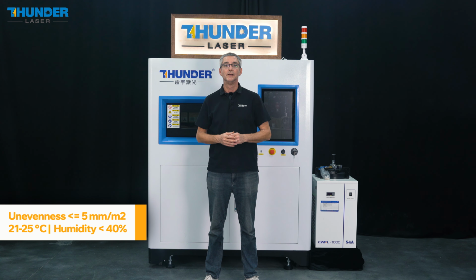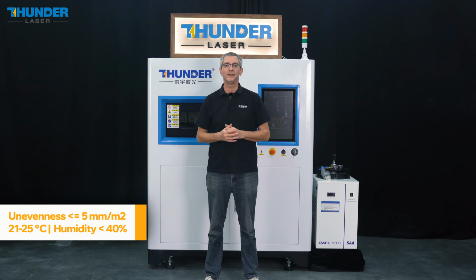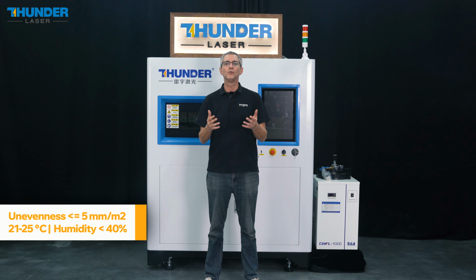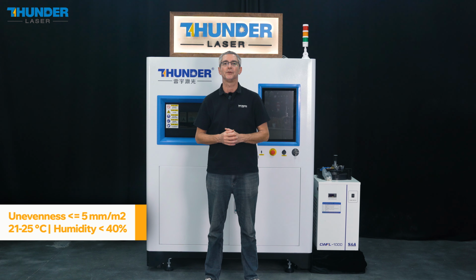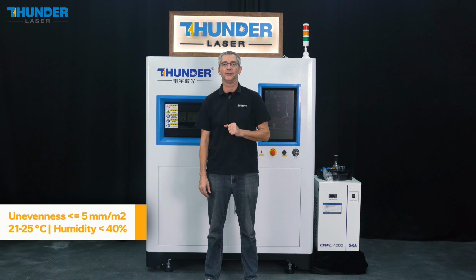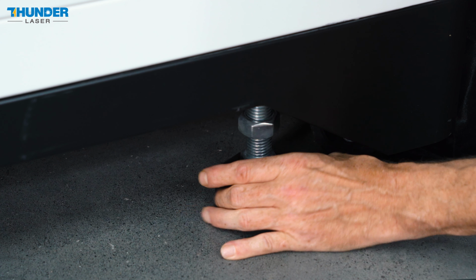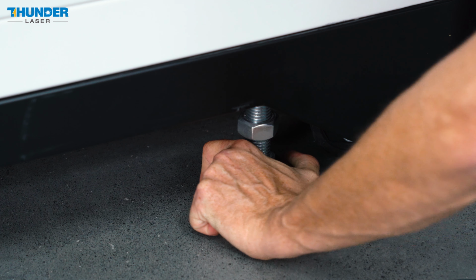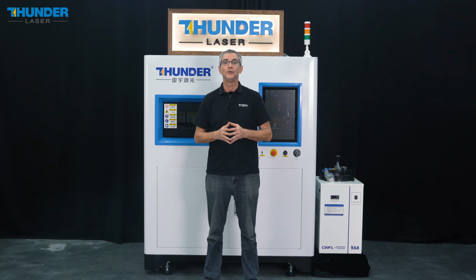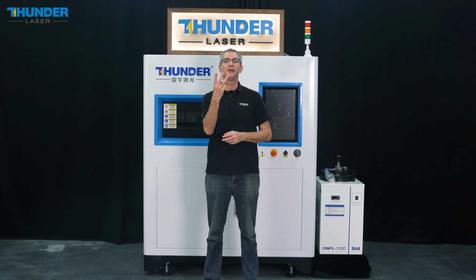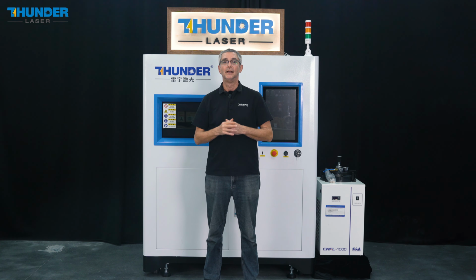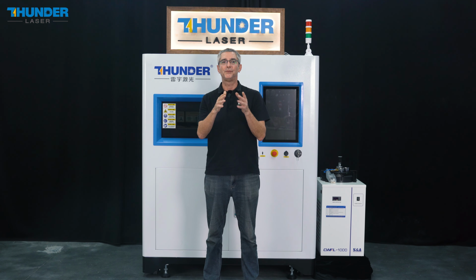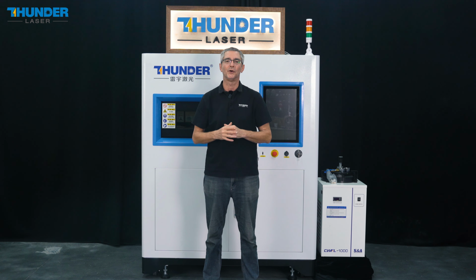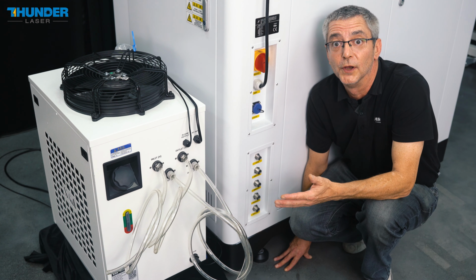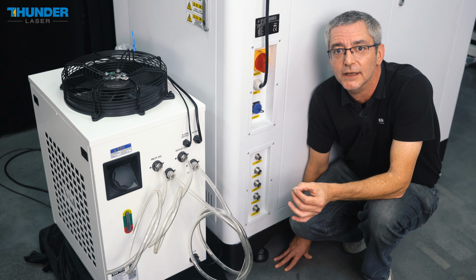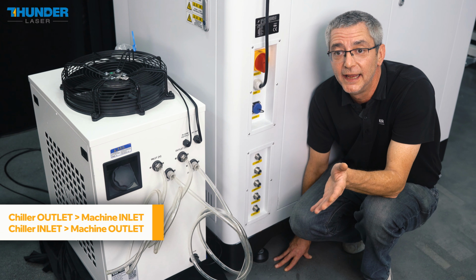The floor must be hard, flat to within 5 mm per square meter and vibration free. Keep the room between 21 and 25 degrees Celsius and the humidity below 40%. Once in position, lower the leveling feet until the machine is firmly fixed. No rocking. Now, 3 connections in a specific order. Gas and water always before the power, always in this order. So cooling comes first. Connect the chiller water hoses in this way, outlet to inlet, inlet to outlet.